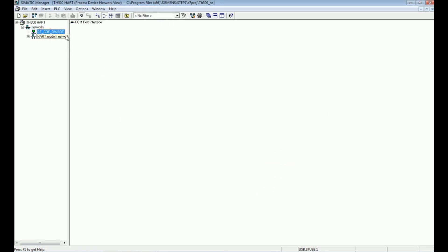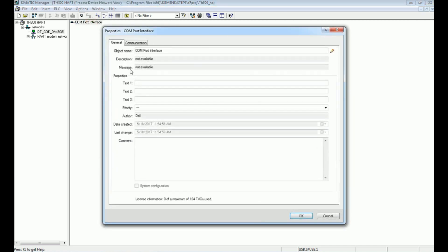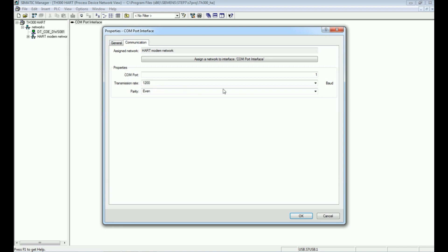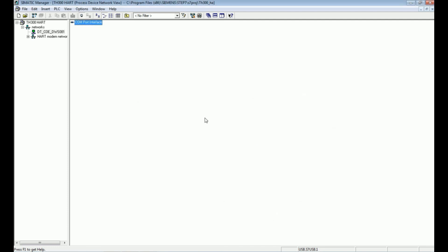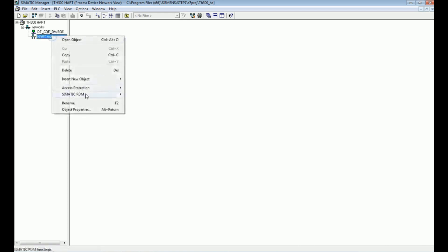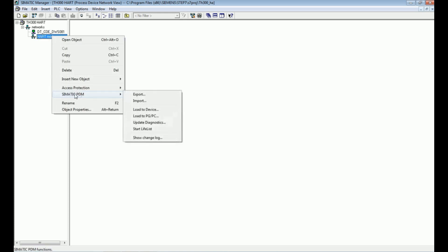We will get the PC name and from the PC we will get the COM port interface. I will open this COM port interface and from the communication option we will select the COM port. Right now the HART modem is connected at COM port number 1, so I will assign the same COM port number to this interface and press OK. We now set this COM port interface to match the HART modem.